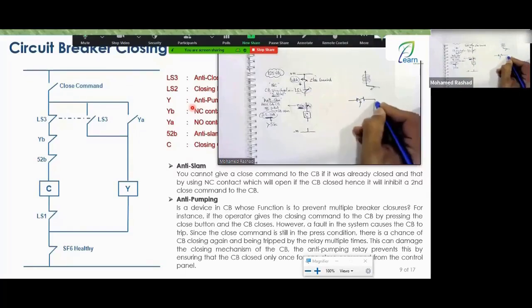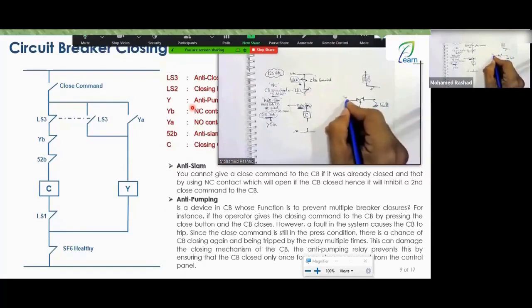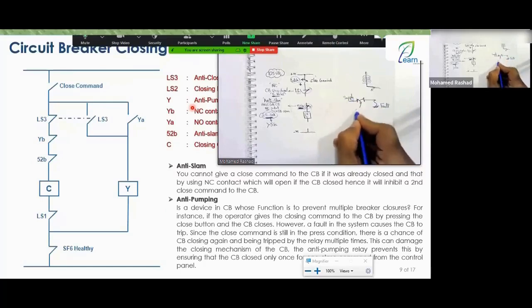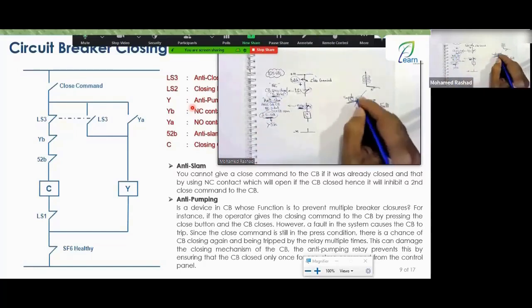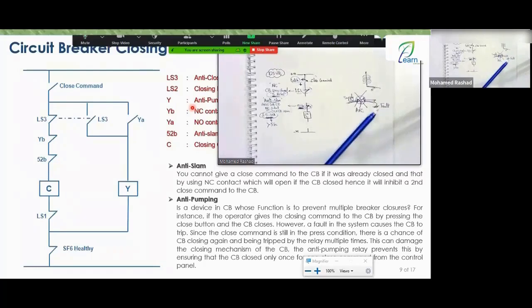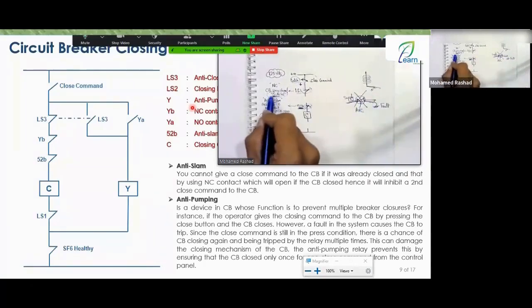The second thing, Engineer Rashad, is that this circuit breaker keeps closing and opening, closing and opening. And it's not just closing and opening normally. There's voltage here and supply there. So when you open and close, there's an arc. You're constantly opening and closing on an arc at close intervals. These poles will heat up and explode. The third thing is that the breaker keeps closing and opening every 5 seconds.